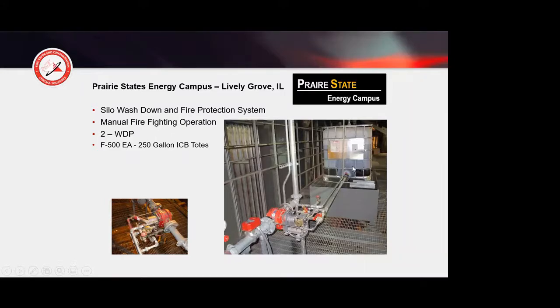In the meantime, this one just used 275 gallons, which happened to be the requirement. So we can just use a standard 275 gallon IBC tote or 1,000-liter tote. We raised the tote and put it on this spill containment area. We often do that only to isolate it away from any forklift traffic you might have. If somebody were to poke a hole in the tote, all the agent would still be captured here. You wouldn't lose the agent. You could just replace the tote, pump the agent back into the tote, and not lose 1,000 liters of agent.